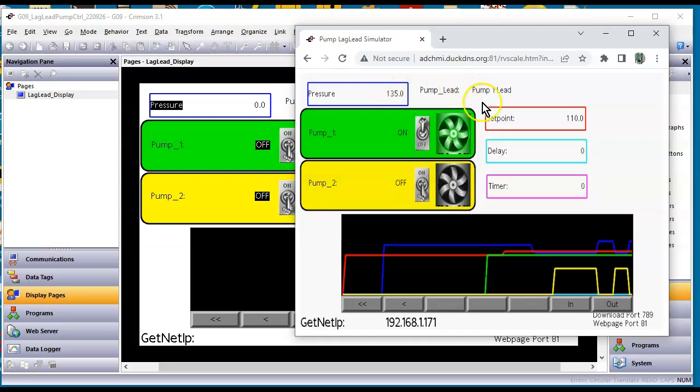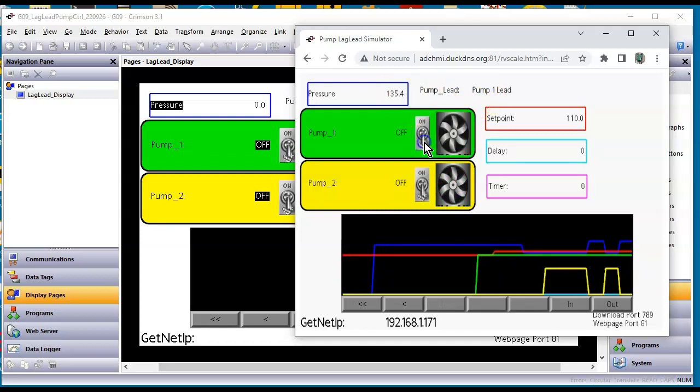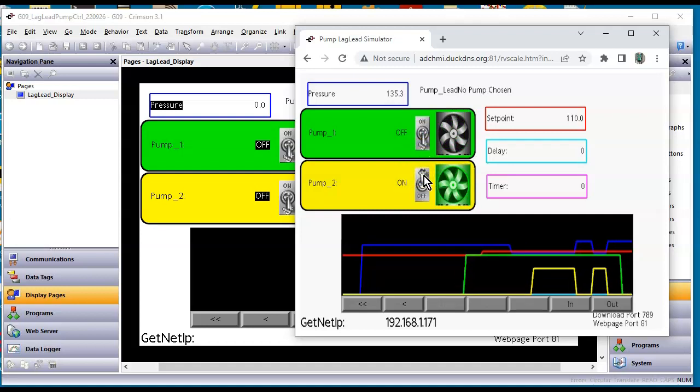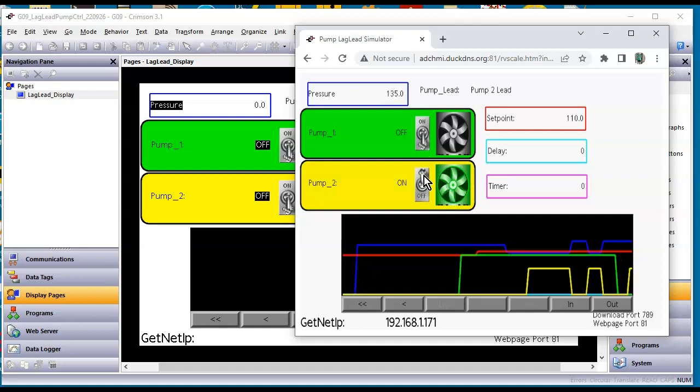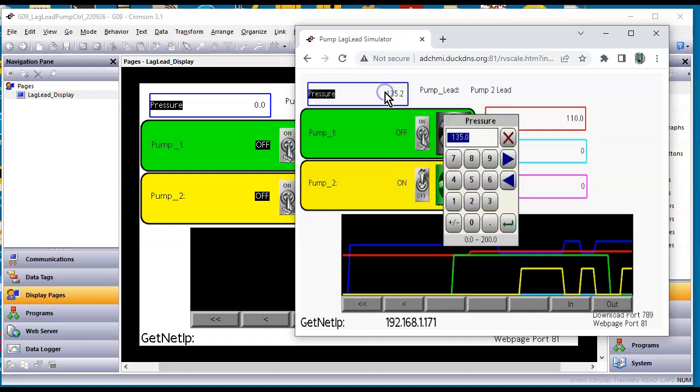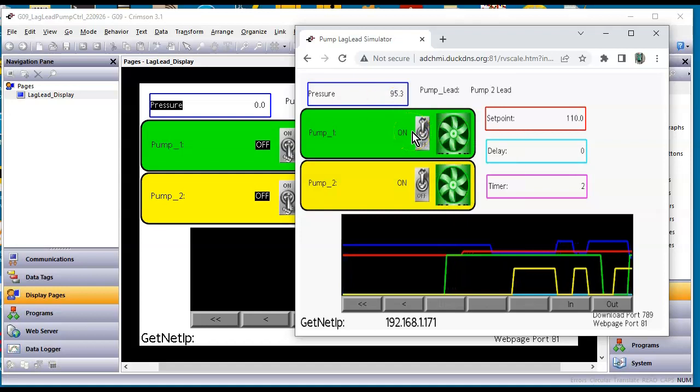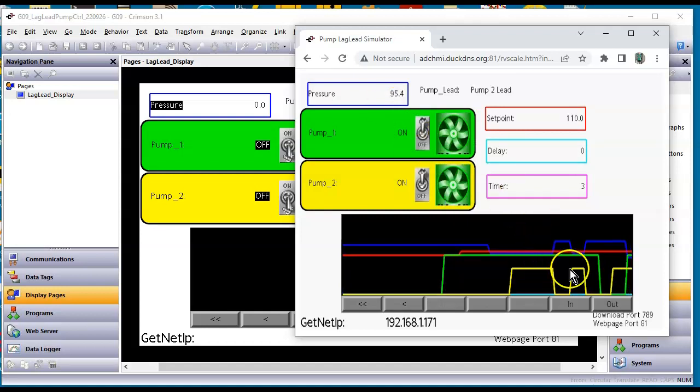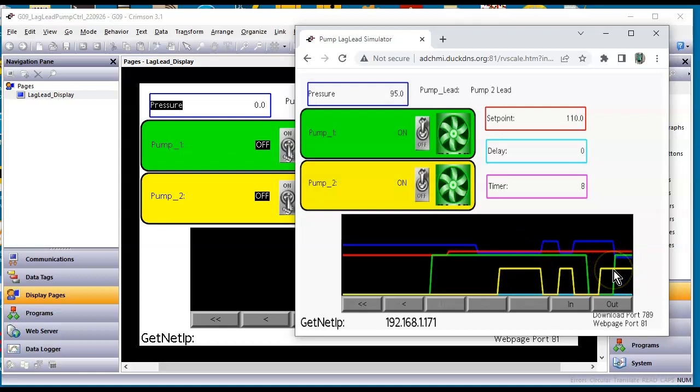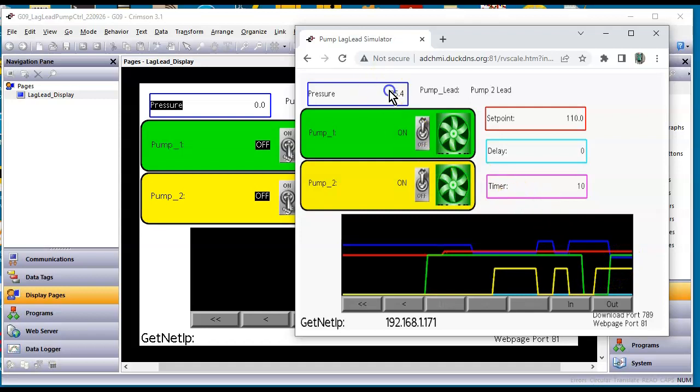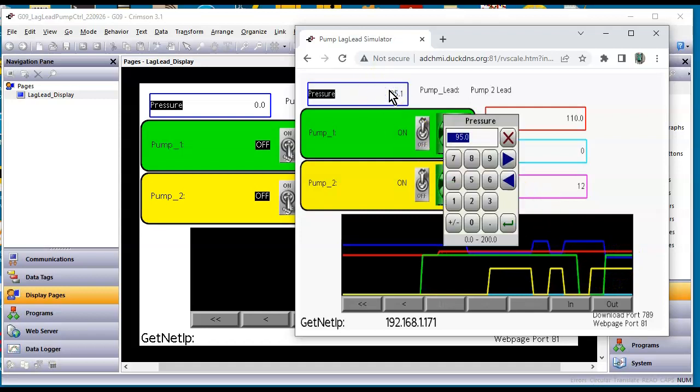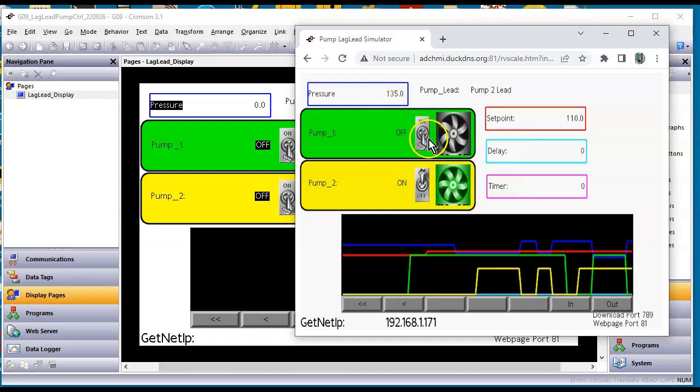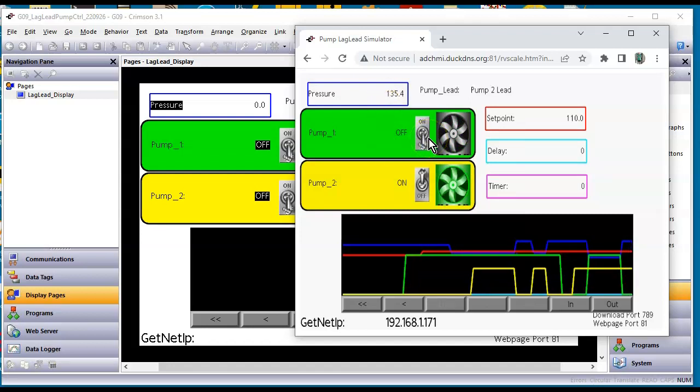All right you also see here there's a pump lead and it says pump one lead. So if I turn this guy off now there's no pump chosen. If I go ahead and say this time I want to start with pump number two, so I can manually do pump number two and again make this below my set point. You'll see that pump one turns on and you'll see you're actually seeing here the lag lead. So here this is the pump number two is leading and now pump one follows, and of course if I raise this above, you'll see that pump number one went off because it was the lagging pump. So that's how that application works.